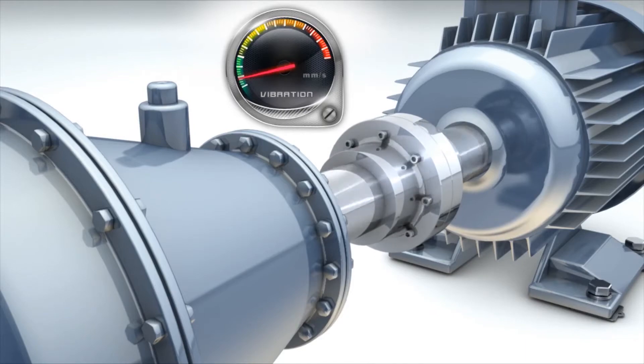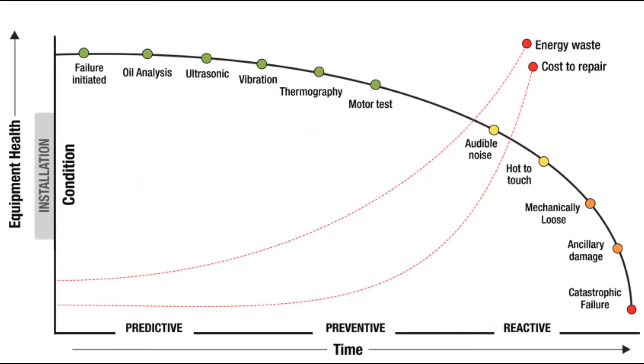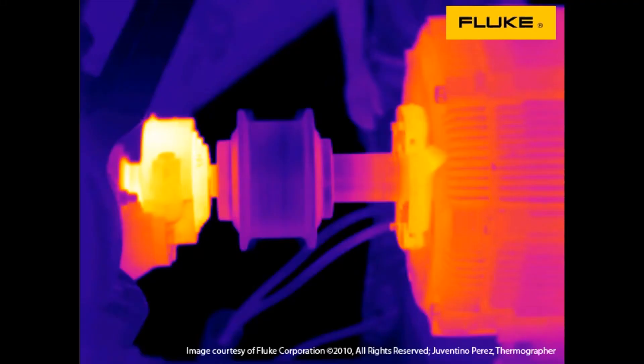Why use vibration before other technologies? Because it is the best practice for when a mechanical fault needs action. Thermography is good, but it is often too late. Temperature increases at the later stages just before failure.